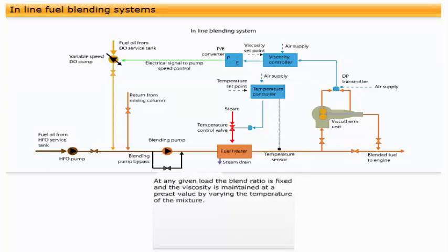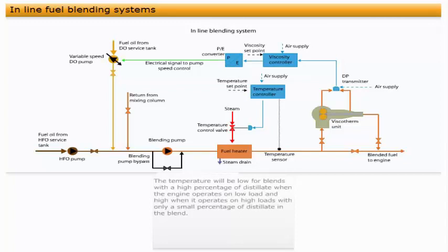At any given load, the blend ratio is fixed, and the viscosity is maintained at a preset value by varying the temperature of the mixture. The temperature will be low for blends with a high percentage of distillate when the engine operates on low load, and high when it operates on high loads with only a small percentage of distillate in the blend.